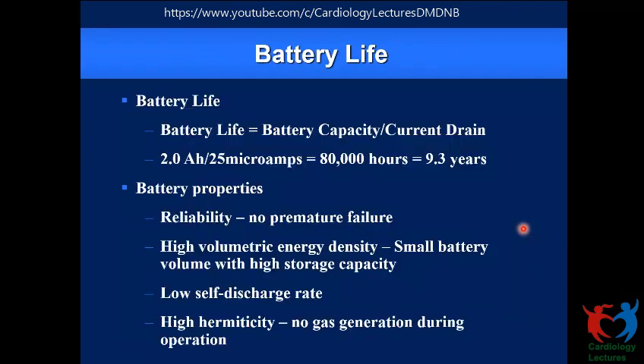That's about considering when to change the pacemaker battery or pacemaker itself, and then a little bit about the life of the battery. The life of the battery is dependent on the battery capacity. Battery capacity is represented as ampere hour. In this case, we have sketched a 2 ampere hour battery. What do we mean by that? If I draw 1 ampere of current from this battery, it will last for 2 hours. So if it is a 1 ampere hour battery and I draw 1 ampere of current continuously for 1 hour, then this battery will last for 1 hour.